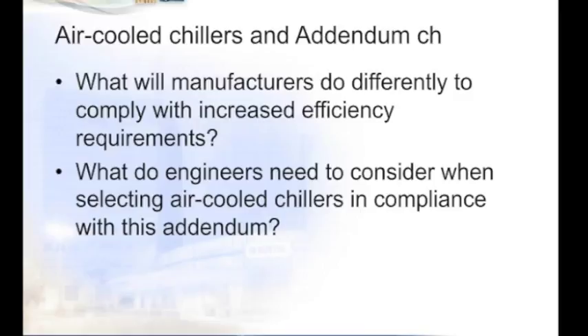Lower efficiency models typically complied with the part load efficiencies, but struggled to meet the full load efficiency requirement with these new updates that will take effect. While this probably isn't a true statement for all manufacturers, it is something that engineers will need to educate themselves about for projects, which will be released after the first of the year in states that have adopted the 2010 version of ASHRAE 90.1. Engineers will need to check in the specific states and municipalities where they do work for the requirements on chiller efficiency compliance and if there are any exemptions that might exist where addendum CH isn't adopted in those local locations.